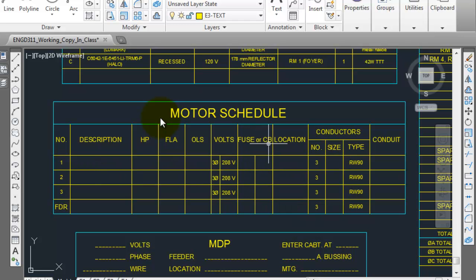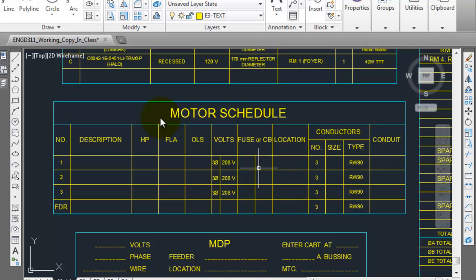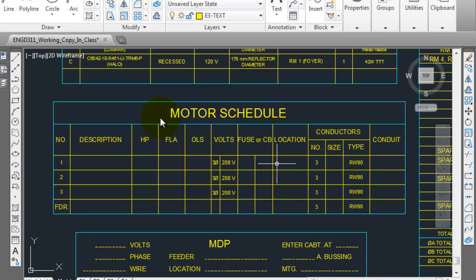Where it says fuse or circuit breaker, we're using circuit breakers, so this is going to be the size of the circuit breaker. Not the calculated value but the actual size of the breaker that you're going to use. So if you determine that you need a 15 amp breaker, you're going to place 15A in that location.